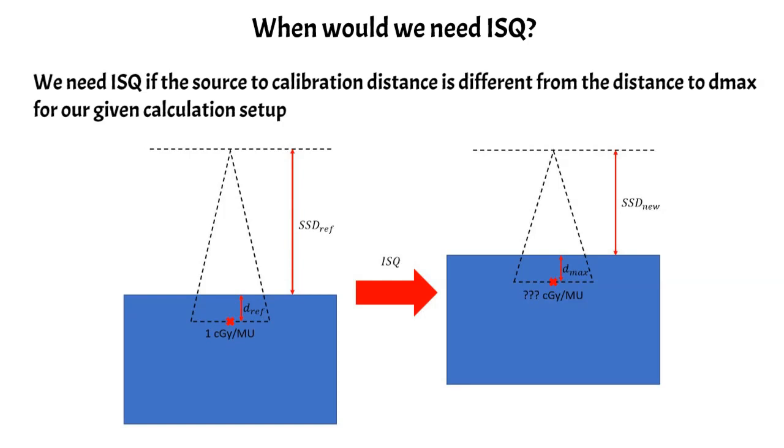So on the left, you can see our calibration condition. So we calibrate our accelerator at a given SSD, at a given depth, and we know the accelerator is giving one centigray per monitor unit in this condition. But if we convert this condition to our treatment geometry that we have, we might not be giving one centigray per MU at the depth of D max here. And remember, the PDD is normalized to D max.